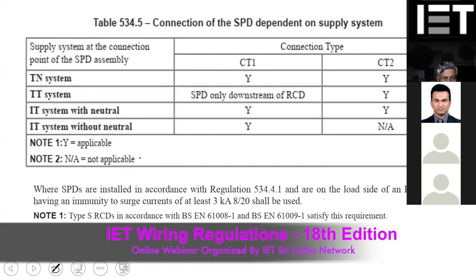In the new regulation, which gives the recommendation on how to use these different connection patterns, you can see that in a TT arrangement the first type is not recommended. If you are using the first type, you have to use it only after the RCD, that is downstream of the RCD. And when you are using it downstream of the RCD, there are other requirements: it must have a withstand immunity of at least 3 kiloampere, and you have to use a type S RCD. Those are the requirements, and they are new additions to the 18th edition. But you can see here that for the TN system, with the type 2 arrangement, you can go with whatever connection pattern.